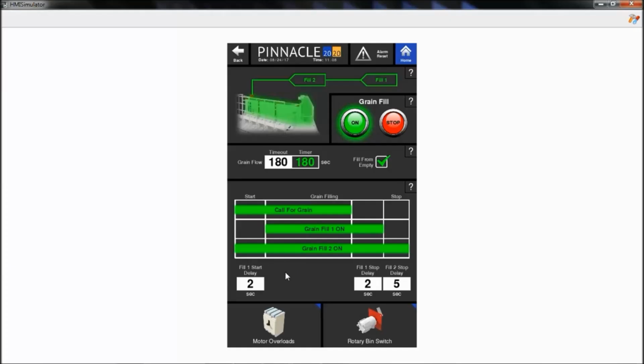The only timer I really recommend we always use is the fill 1 start delay. In every scenario, you want a delay between your call for grain and when the motor starts. Otherwise, that motor is going to be toggling on and off very frequently.